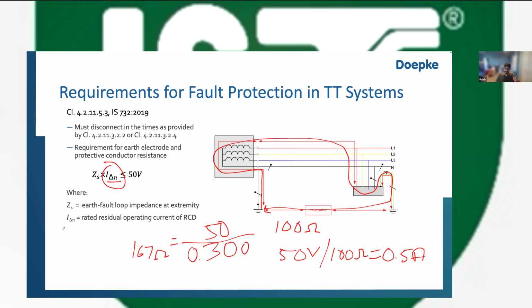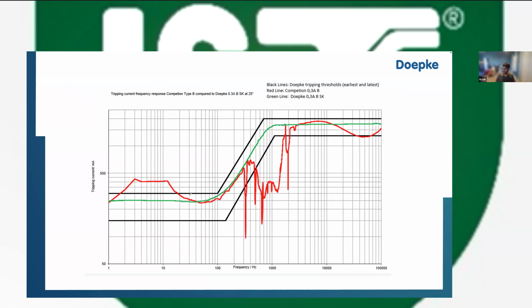But the most important thing, sir, is to make sure that you have the right type of RCD. Because, as I mentioned here, if the RCD is a type A or a type B, which is not tuned to the correct frequency, or a type AC, two things may happen. Number one, it may get stunned, as the previous person had asked, and then it will not trip at all. Or number two, because the chopper frequency is very high, and that is the nature of the residual current, your 300 milliampere RCD may trip at, for example, 60 milliamperes, and then you have nuisance tripping.